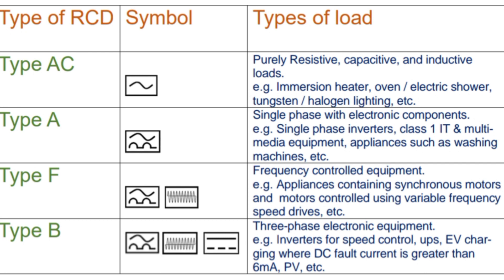The type A is identified by this symbol. The type A can be used in single-phase circuits with electronic components. Examples of these electronic components are single-phase inverters, class 1 IT and multimedia equipment, and appliances such as washing machines. This type of RCD can also withstand a superimposed smooth DC current up to 6 milliamp, and it will also detect the sinusoidal residual current that the type AC can. So the type A can work perfectly wherever the type AC can work, but it has an additional advantage of being able to work on single-phase rectifying circuits, which could create a pulsating DC residual current.